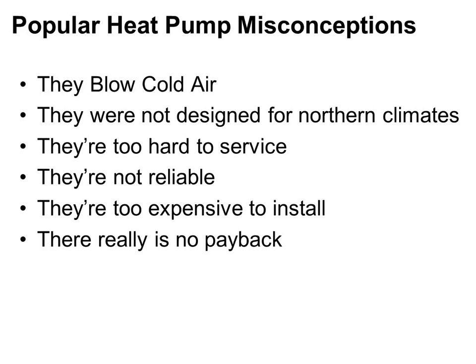There's been some concern that perhaps they're not reliable. In fact, you'll even hear some thermostat manufacturers say, oh, our thermostat has an emergency heat switch, so when your heat pump fails, you can put your electric heater on, right? There's no data that supports that heat pumps fail more than other air conditioner types, right? It's just a misconception that people have. Because of that cold blow thing, they think it's not working, but there's no reliability difference.